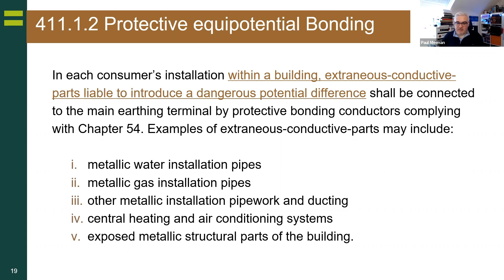So obviously anything extraneous - extraneous is not part of the electrical installation - at earth potential, liable to introduce potentials greater than earth. Metallic water pipes, gas, other metallic pipework and ducting, central heating, aircon, and metallic structures. That's not changed, that's bread and butter.